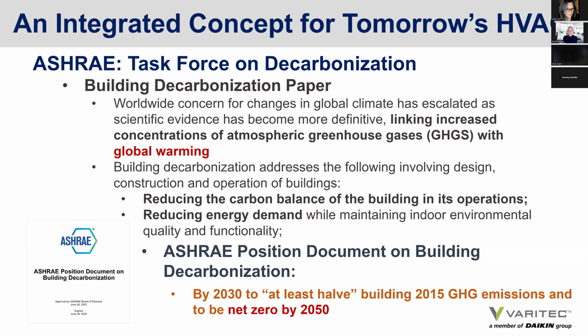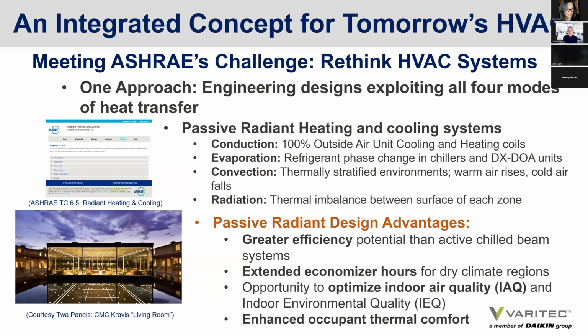So one approach, of course, is to rethink how we do HVAC, take advantage of passive systems that offer passive heat transfer within the zones of a building. And one of those solutions, of course, is using radiant heating and cooling systems that use the heat transfer modes of conduction, evaporation, convection, and radiation in the system to achieve greater efficiency, exploit the added economizer hours or free cooling available with these systems, provide better indoor air quality to meet the indoor air quality and indoor environmental quality standards, and to create better thermal comfort.